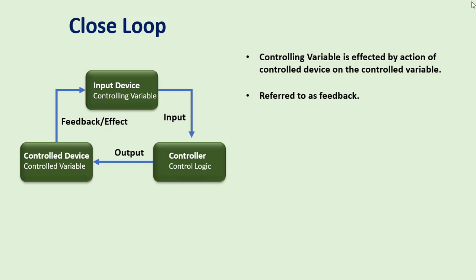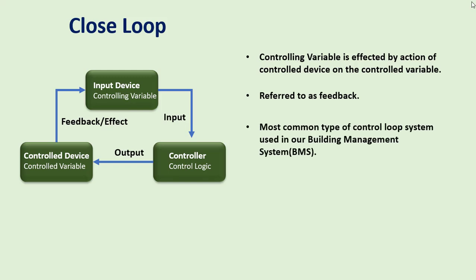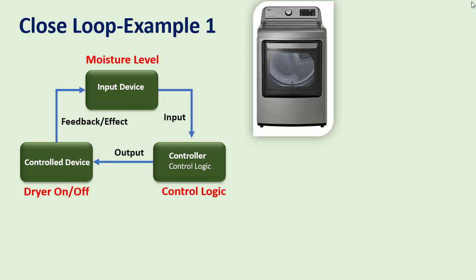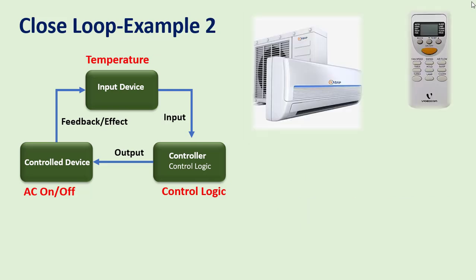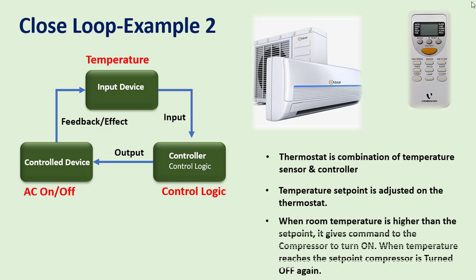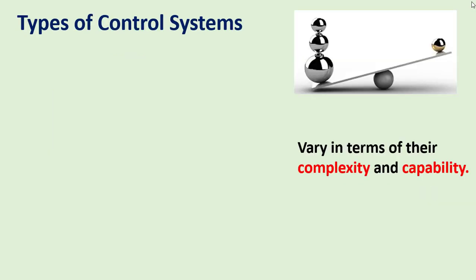In a closed control loop, the controlling variable is affected by the actions of the control device on the controlled variable — this is referred to as feedback. This is the most common type of control loop used in BMS. For example, if we measure the moisture level of the laundry and feed that data to the controller, the controller will compare the moisture level to a setpoint, and when it drops below a certain level the dryer will be turned off. Another example is temperature control inside a room using a thermostat — a combination of temperature sensor and controller. When room temperature is higher than the setpoint it commands the compressor to turn on, and when temperature reaches the setpoint the compressor is turned off.